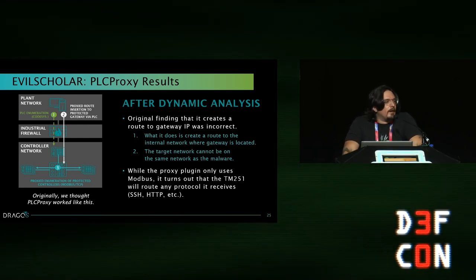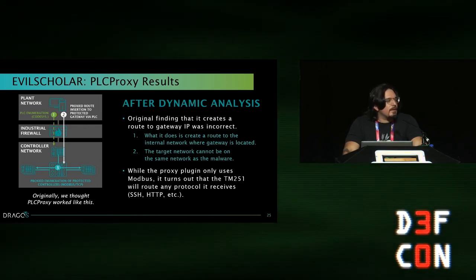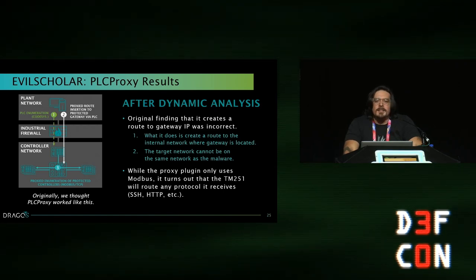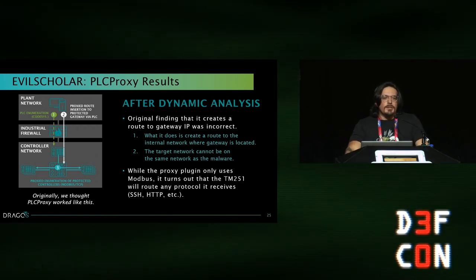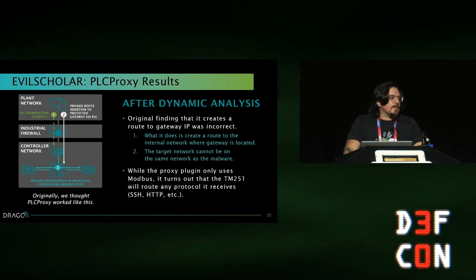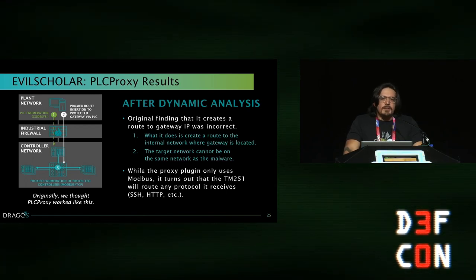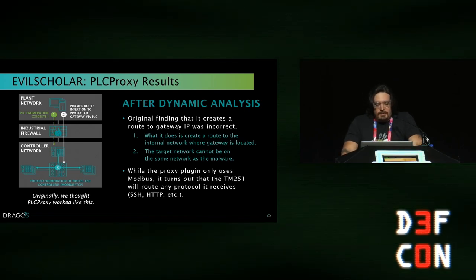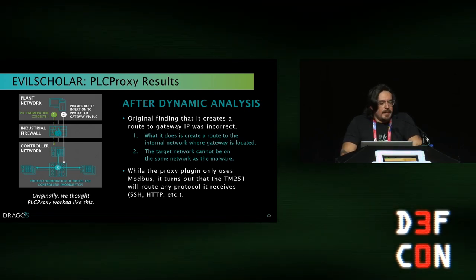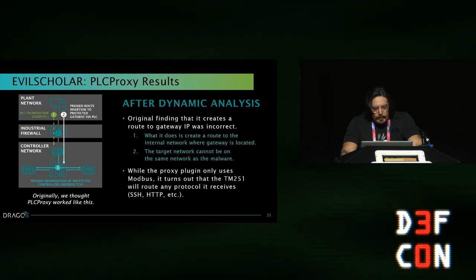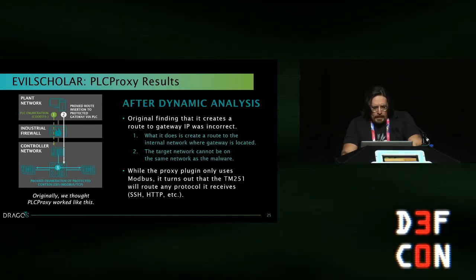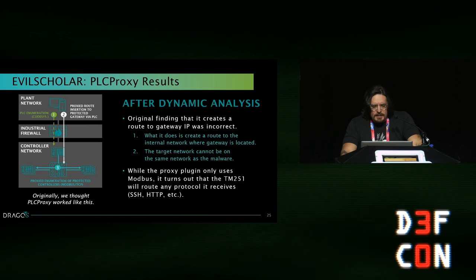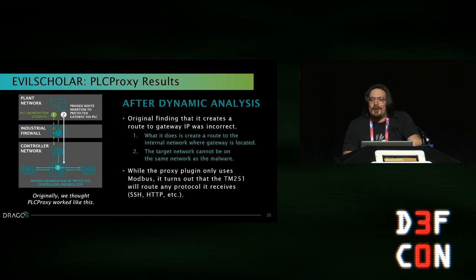The PLC proxy concept: you have an internal PLC network behind an industrial firewall. The firewall ensures engineering workstations only talk to their responsible PLCs. Evil Scholar queries for the CODESYS gateway IP and creates a route through the target Schneider Electric PLC to a network the malware isn't on. It turned out it's just sending traffic to the network and letting the TM251 route wherever it wants. Even nastier: the TM251 won't just proxy Modbus traffic — it will proxy anything: SSH, HTTP commands, arbitrary ICS protocols. It just got worse.